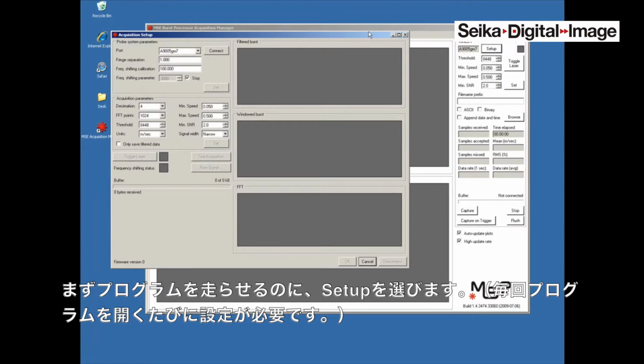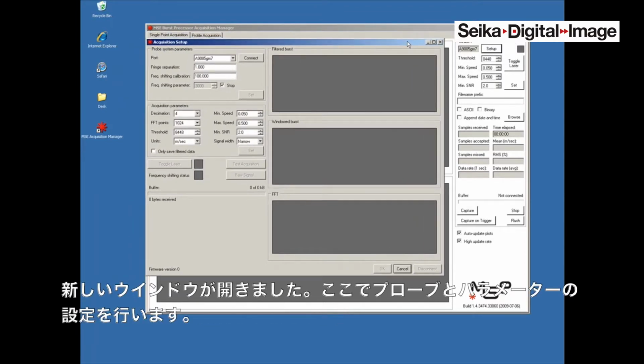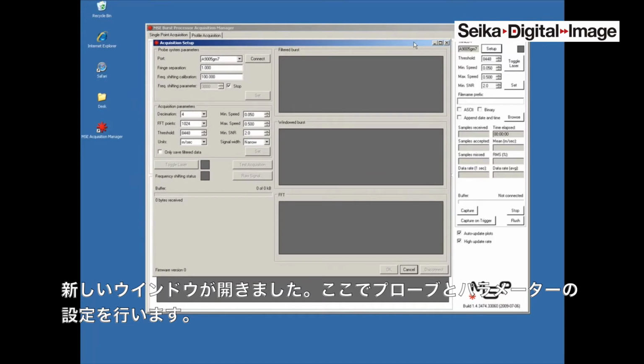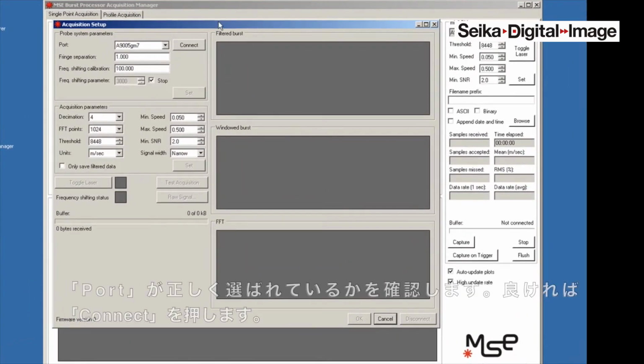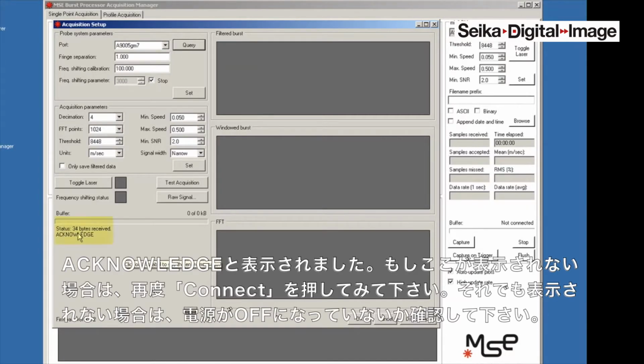The setup starts with a new page, and this page is the setup for the LDV probe as well as for the program parameters. To connect, you need to look for the correct port setting. It usually assigns the correct port in here, but if not, you need to look for it and push connect, and then look for acknowledge here. If the acknowledge doesn't come, you repeat the process maybe 2 times and you get acknowledge. If it still doesn't come, you look at the electronics and make sure that it's on, and otherwise it should come out.